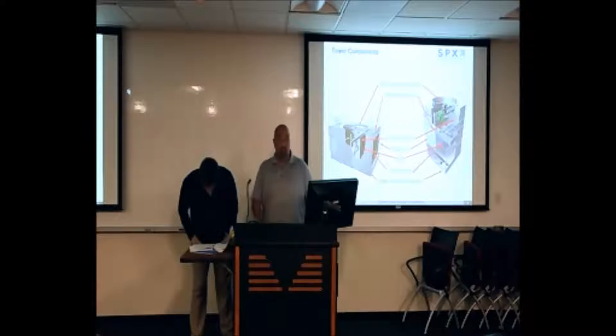And your O&M, if you guys want it on disc, I'll get it to you on disc. But your O&M has actual specific blade pitch. So if you guys ever were to re-pitch the blade, or something were to happen to the motor where you have to take the fan out or anything like that, you're going to re-pitch the blades. All that information is specific to your guys' tower. So if the angle is set at 9.2 degrees or something like that, it's specific to that tower. It's not a standard. But everything is in the manuals.